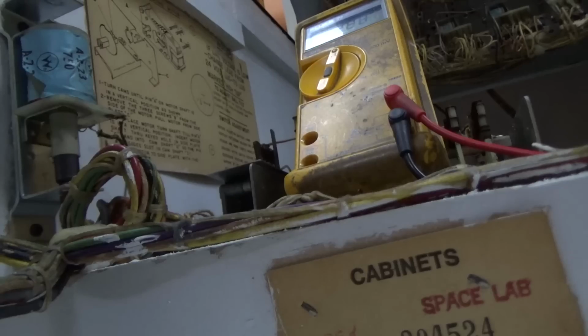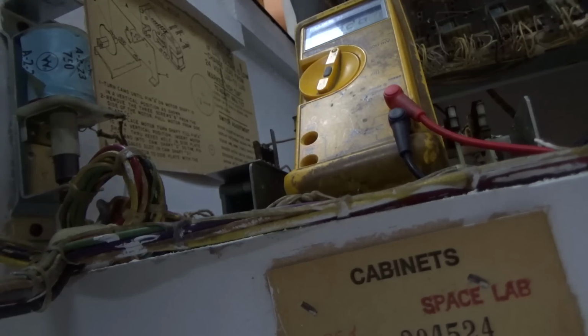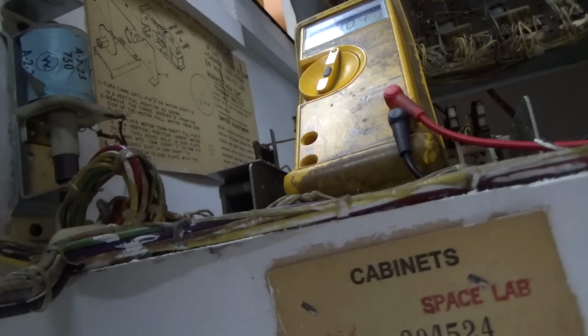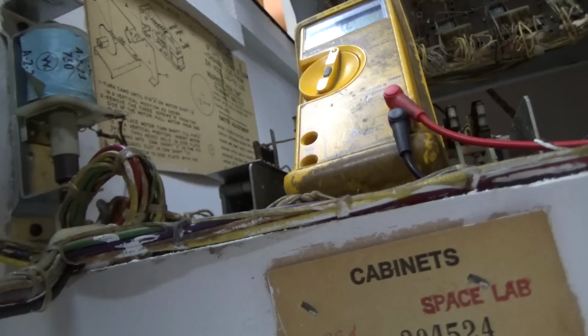All right, so I've got my trusty old fluke meter set on AC. I'm going to put the ground, or black probe, on the common, and then we're going to check our light bulb voltage, the 6 volts. So we've got 6.8 volts, and then if I go over to the 24 volt, we've got 29.82 volts. Notice those are real high.